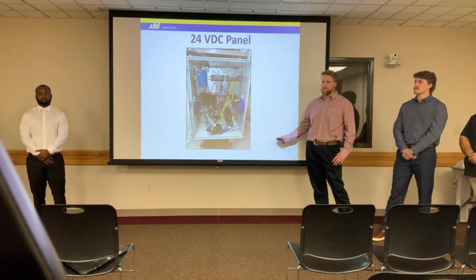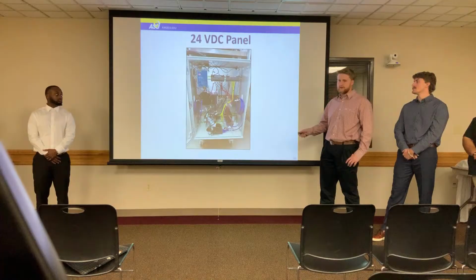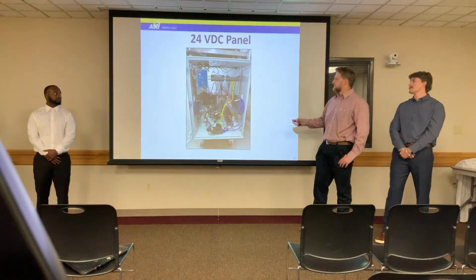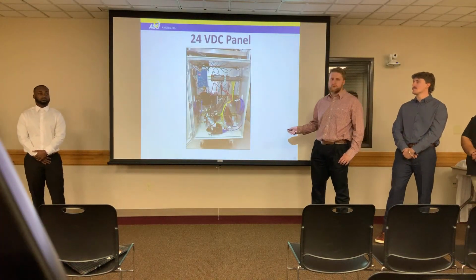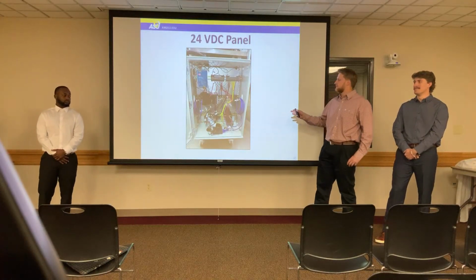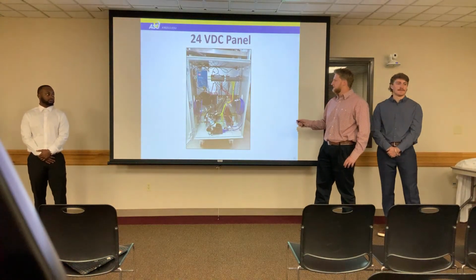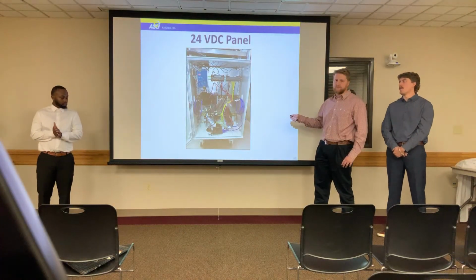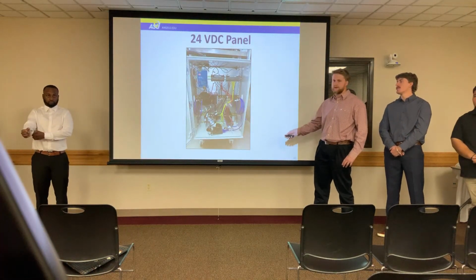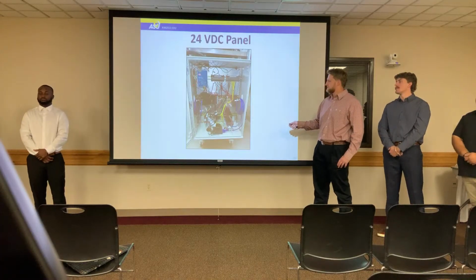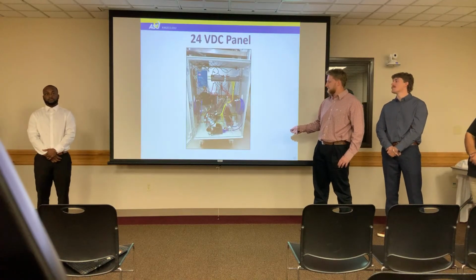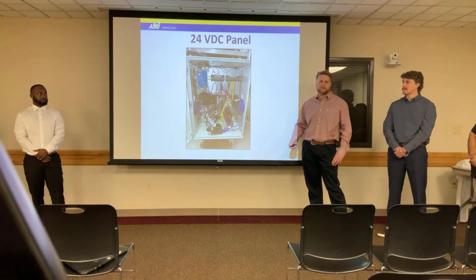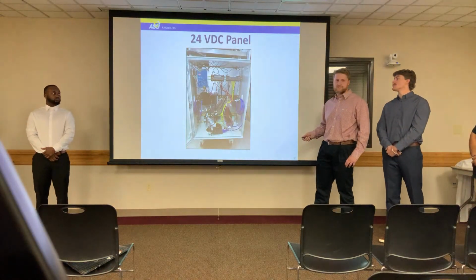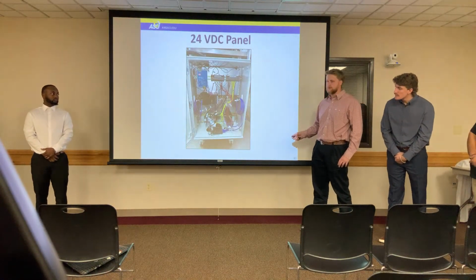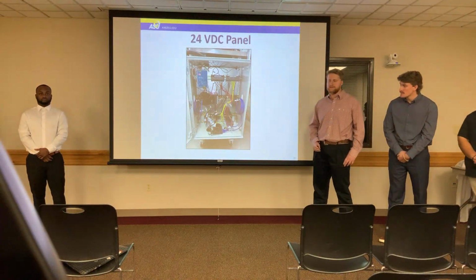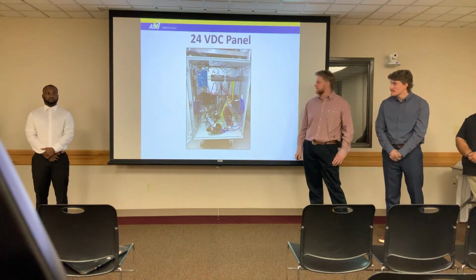And then this is our last panel, the 24 volt panel, where most of our components are. So this is the power supply, which changes our 240 volts down to 24 volts. And then from there, it runs into a positive and negative bus bar, which are used to power the rest of our components. So we have the PLC here, our load cell amplifier, our relays, which power all the solenoids for airflow, and the emergency dump. And then our safety controller, which takes inputs from our safety fixtures controlled by the PLC.